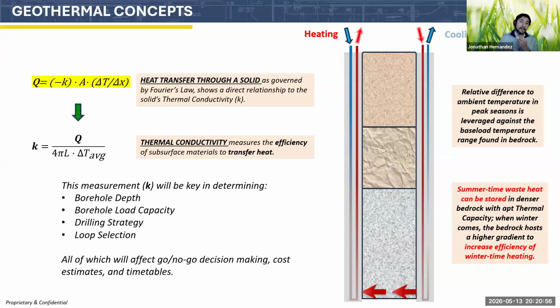That will be a factor in determining how many boreholes, how deep, the kind of drilling strategy that's required. It'll affect your budget, the permitting, the scheduling, and even loop selections. There's more than one type of loop. There are high performance exchangers that can get you 10 tons, 12,000 BTUs per ton, or regular loops that can get you, let's say, 3 to 5 tons per hole. It all depends on the conductivity and on the well design, which is based on that conductivity.